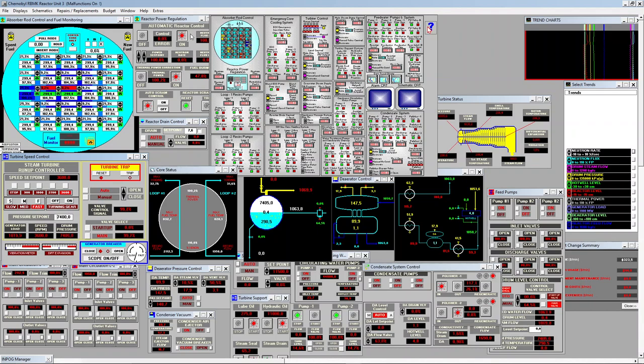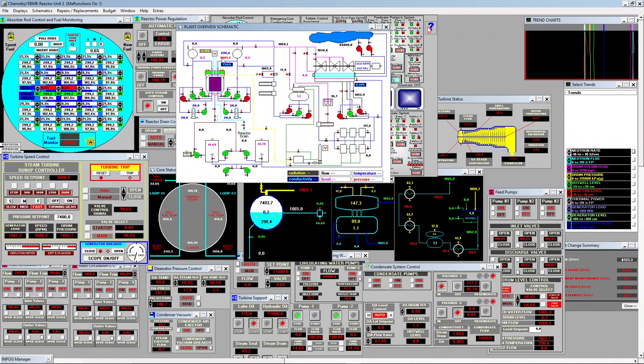So while we have the same neutron flux and same thermal power, it seems that less of this power reaches the turbine. And this is because you have less transfer between the reactor and the drum. I will go to the schematic. This is a loop where basically water circulates like this. And approximately one-fifth of the water converts into steam and goes to the turbine.